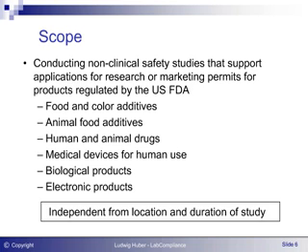This slide shows the scope of GLPs. They regulate all non-clinical safety studies that support or are intended to support applications for research or marketing permits for products regulated by the FDA or by similar national legislation. This includes medicinal and veterinary drugs, aroma and color additives in food, nutrition supplements, and livestock and biological products. The duration of the study is of no importance, nor is where the study is performed. If a sponsor subcontracts part of a GLP study to a subcontractor, they have to comply in the same way.